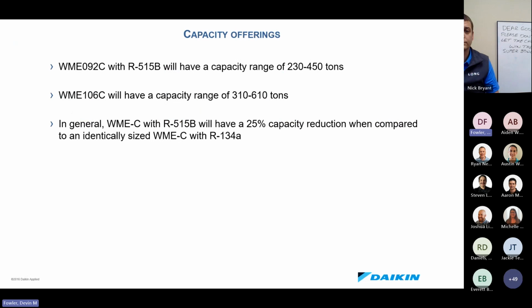With these capacity offerings, a WME 092 single with 515B will have a capacity range of 230 to 450 tons. The 106 singles will have a capacity range of 310 to 610 tons. This takes our traditional capacity with an 092 from 400 to 600 and a WME 106 from 600 to 800. It does reduce it. Like I said, just something to be cognizant about. If you are going to do a retrofit application, you'll need to make sure you're going to choose the right refrigerant for that application so that you won't lose any of your total load. In general, WME-C with 515B will have a 25% capacity reduction when compared to an identically sized WME machine with 134A.